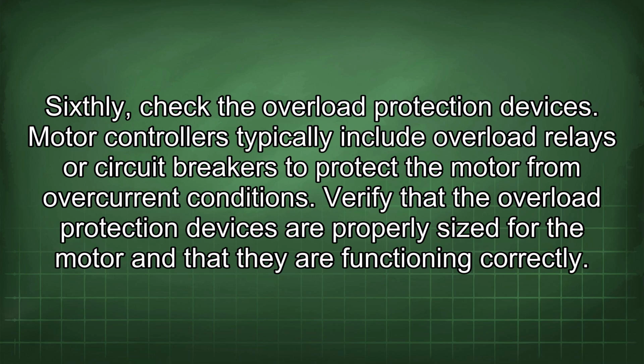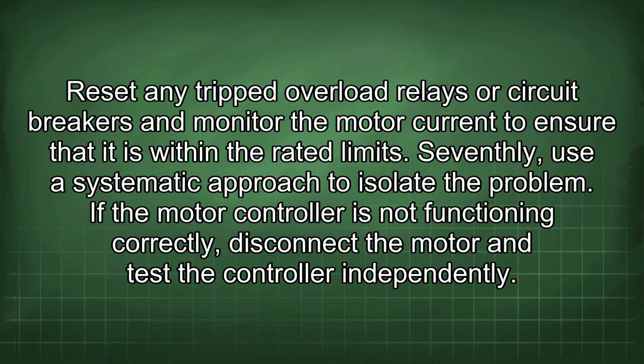Sixthly, check the overload protection devices. Motor controllers typically include overload relays or circuit breakers to protect the motor from overcurrent conditions. Verify that the overload protection devices are properly sized for the motor and that they are functioning correctly. Reset any tripped overload relays or circuit breakers and monitor the motor current to ensure that it is within the rated limits.